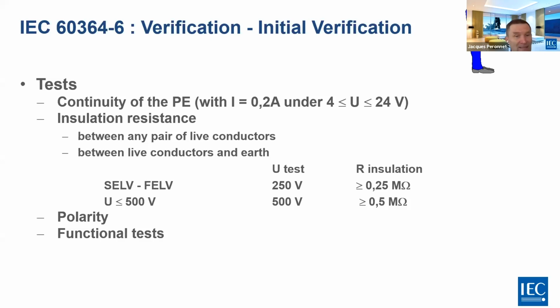You also have to make some tests. As I mentioned, it's very important to make sure that your earthing arrangements are correct and at the right value, in order to make sure that the measure you implement for automatic disconnection of supply, which is the protection of people, will operate correctly. So the continuity of the PE is key. PE is protective earthing.